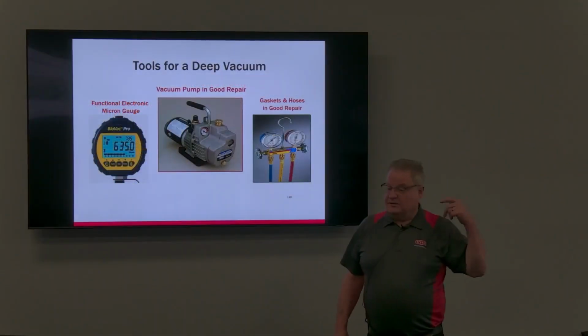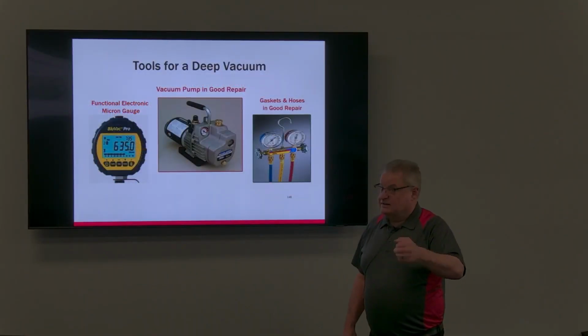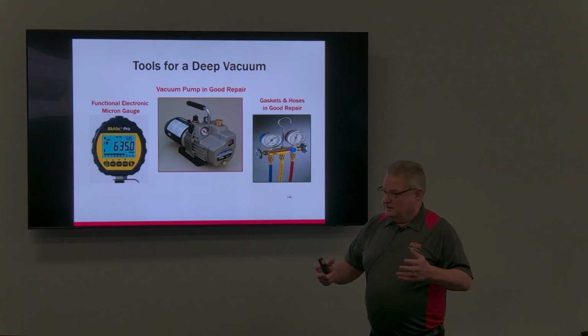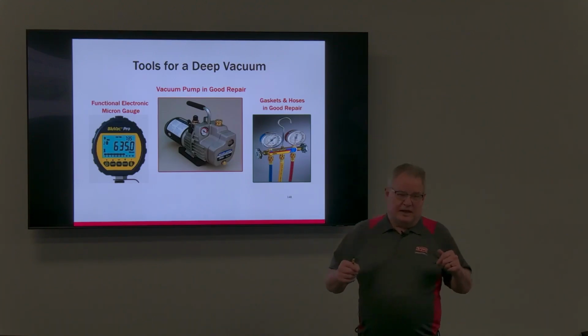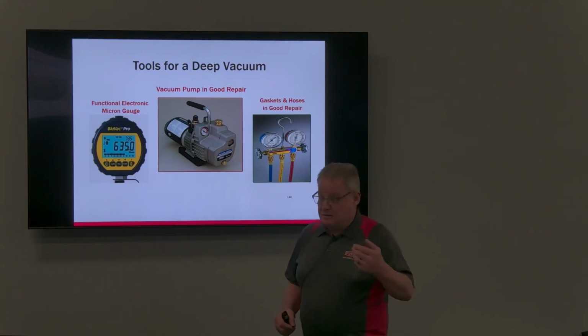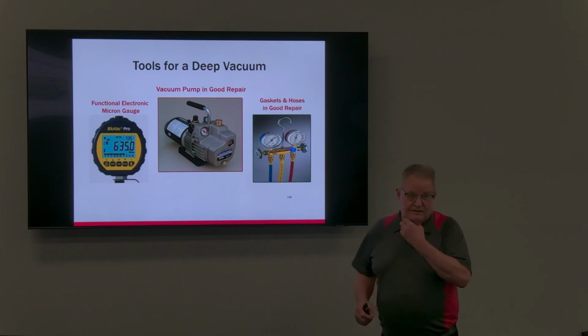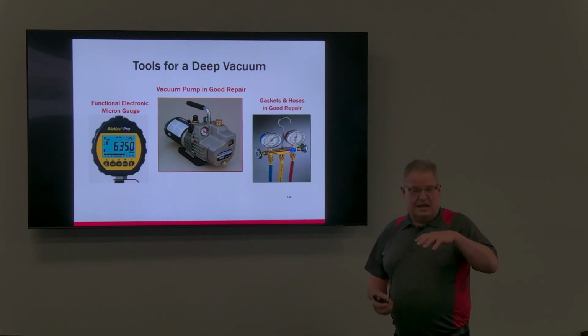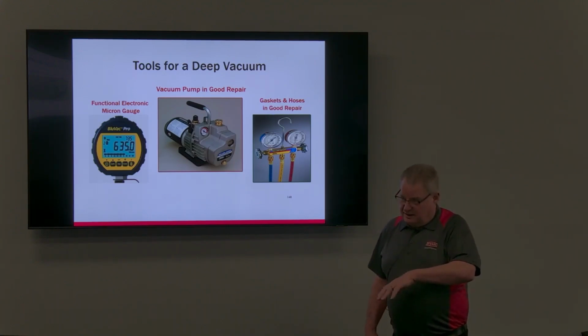You go out in the branch, or if you've ever seen a can of POE oil, it's a metal can. If you look at a can of mineral oil, it's a plastic jug like antifreeze. The reason for that is because the POE will actually suck the water right through the plastic. And if you've been around long enough, when it first came out, it came in a plastic jug, and the jugs would be so swelled up you couldn't get it to stand up on a shelf. So that's why they switched it to metal cans.